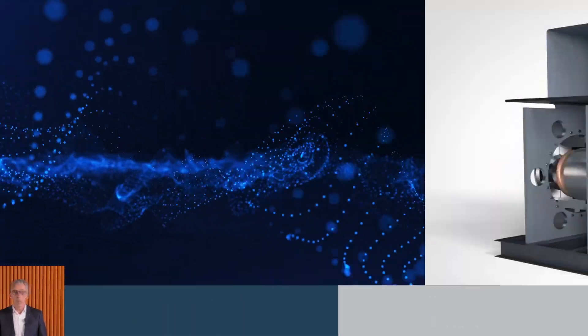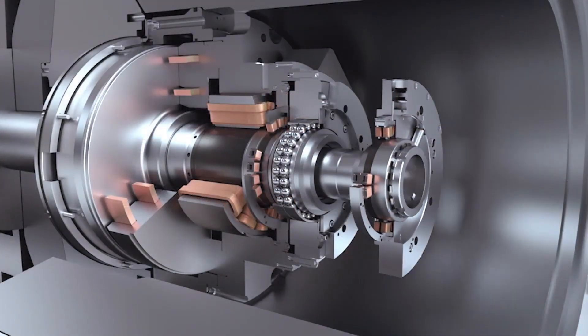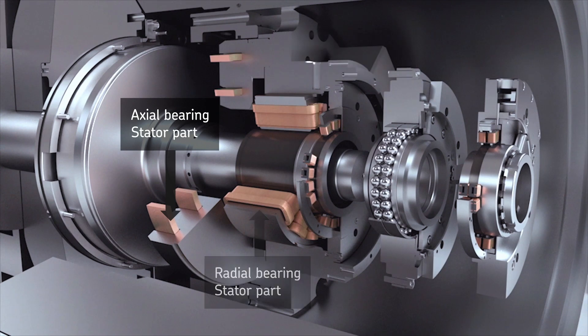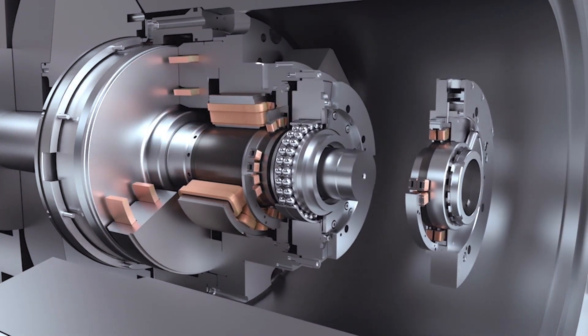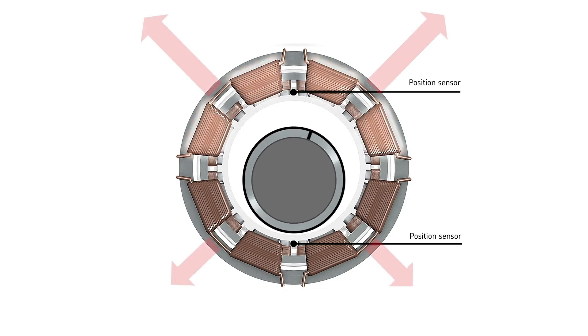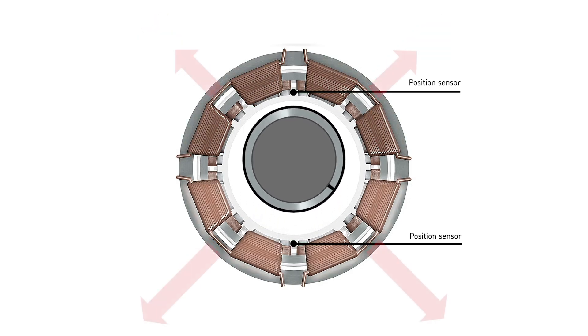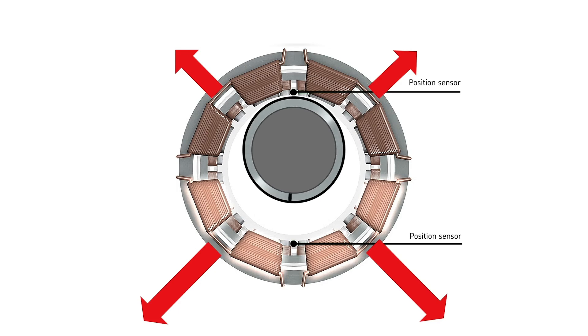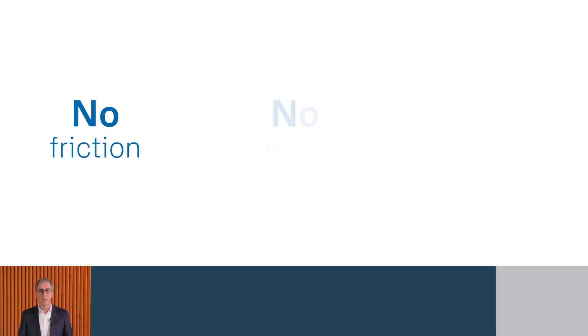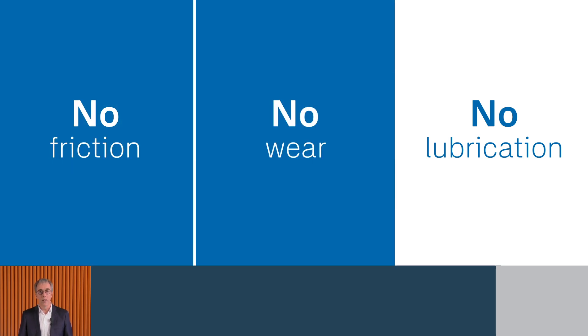Here is how it works. There is no contact between the rotating and stationary parts of a magnetic bearing. This means zero friction, no mechanical wear, no need for an oil lube system, and it's virtually maintenance-free. As the shaft rotates, proprietary position sensing technology tracks its precise position. A high-speed signal processing system continually adjusts the current flowing to the coil actuators on the stator, keeping the shaft floating — or levitating — within the bearing. This means no friction whatsoever, no wear, no need for oil.